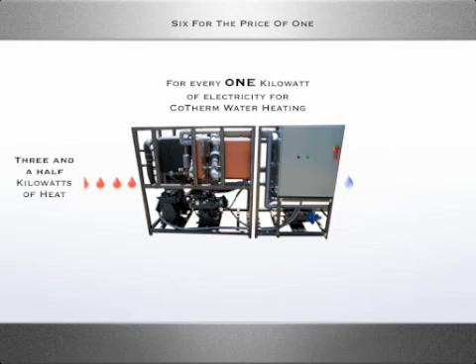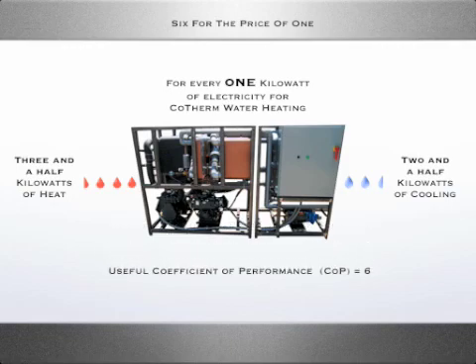Let's look at it this way: 6 for the price of 1. For every 1 kW of electricity used by Cotherm, the facility receives 3.5 kW of heat and 2.5 kW of cooling. Traditional heat pumps, on the other hand, give heating or cooling, but not both benefits at the same time. This is referred to as having a useful coefficient of performance equivalent to 6.